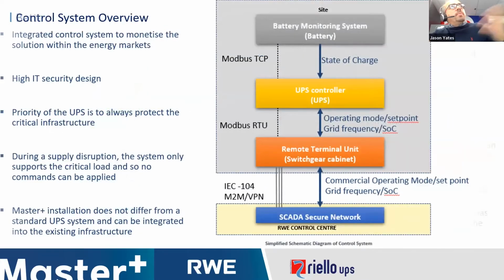Obviously, with the UPS and the battery system, there was a requirement to have a fully integrated control system. Here, the integrated control system's priority was to monetize the solution within the energy markets. Obviously, it had to provide a high IT security design. The priority of the UPS is always to protect the critical infrastructure on site. During a main supply disruption, the system only supported the critical load, and therefore they could not apply any commands to the system. Basically, the Master Plus is a standard UPS installation, and therefore it can be integrated into an existing infrastructure.